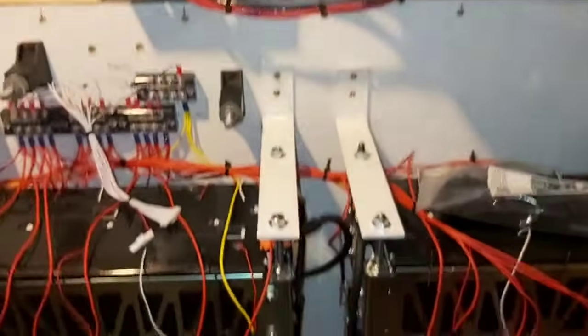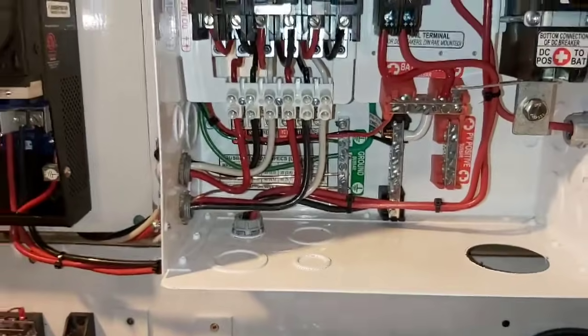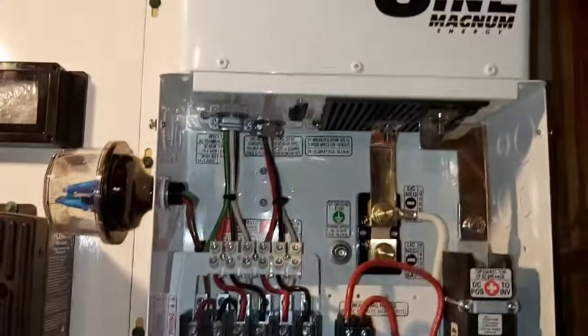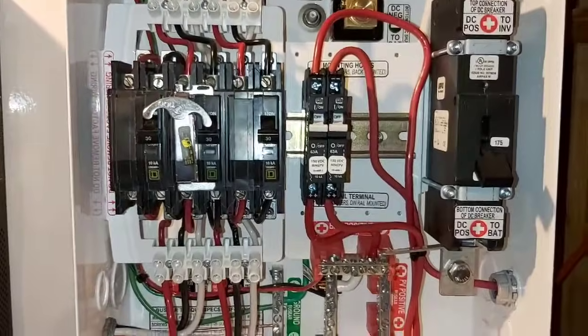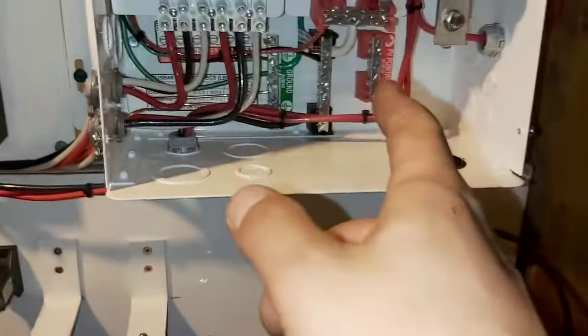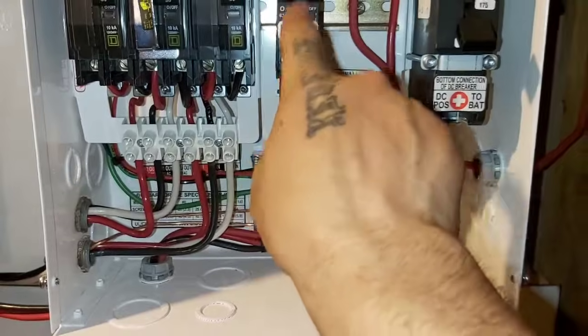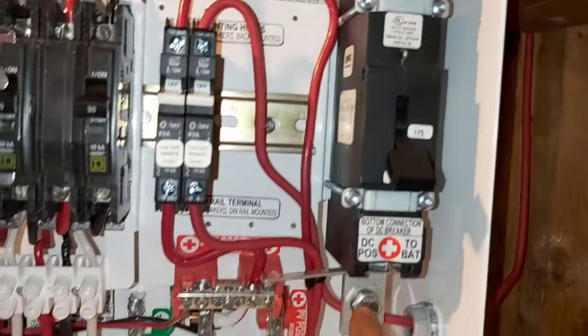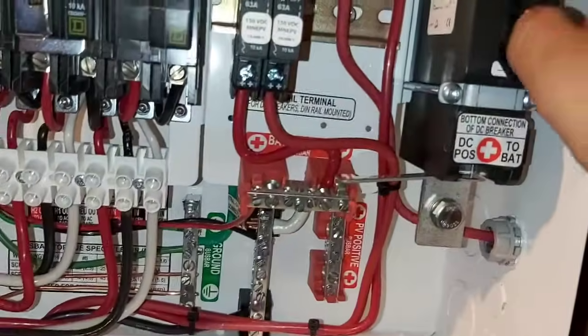Another day in, a little bit closer. We got pretty much all the AC, everything hooked up in here. I got the DC panels, the batteries, the controller to the battery, and the panels. They aren't hooked up out there yet, but they're all hooked up in here. This will be the controller on/off, and this will be the panels on/off. I'm just using this as my main bus bar. It does go to the bottom side of this breaker, so you can still charge and have the inverter off.